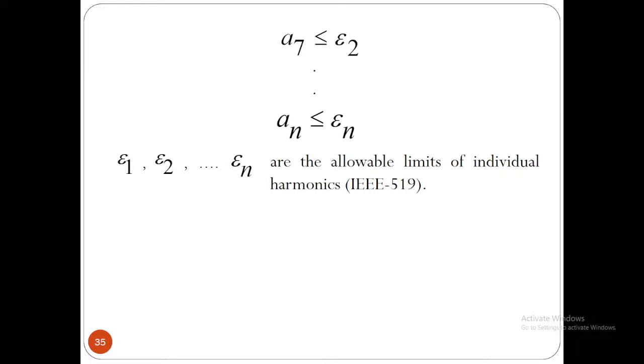Now here we are considering a 66 kV system, because in the Indian system we are not concerned with 69 kV. We are concerned with 66 kV or 132 kV. So we are limiting it to 66 kV. And there also they have set the THD limit. How to calculate it? 5%, considering up to the 30th harmonic. You have to consider up to 30, not up to the 10th or 15th or 20th. Up to the 30th harmonic you have to consider for computation of THD, and then it should not be more than 5%, and the individual harmonics should not be more than 3%. So that is the standard practice in IEEE 519. That's why we have set this value to epsilon 1, epsilon 2 and so on. So you can set up to 5% or 0.05 like that.